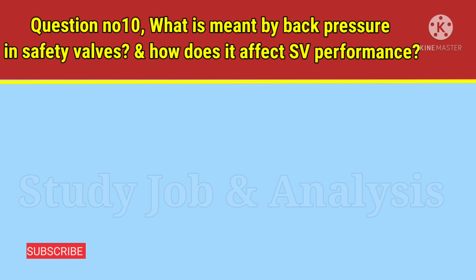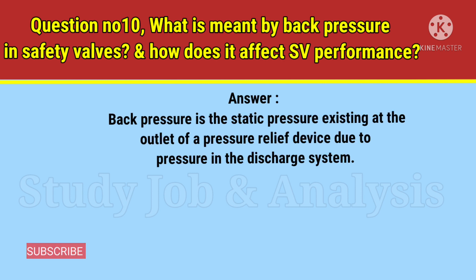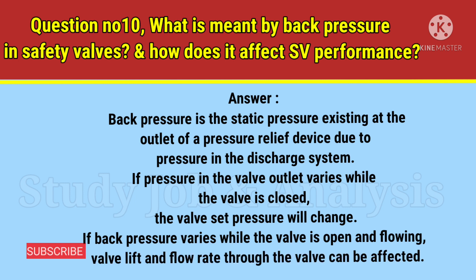Question number ten: what is meant by back pressure in safety valves and how does it affect safety valve performance? Answer: Back pressure is the static pressure existing at the outlet of a pressure relief device due to pressure in the discharge system. If pressure at the valve outlet varies while the valve is closed, the valve set pressure will change. If back pressure varies while the valve is open and flowing, valve lift and flow rate through the valve can be affected.